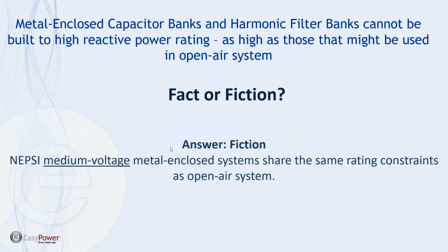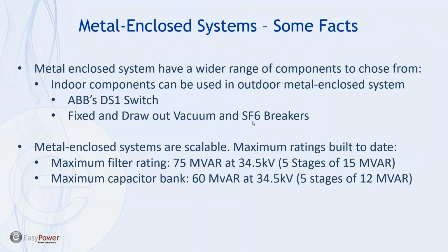So on to the next myth. Metal-enclosed capacitor banks and harmonic filter banks cannot be built to reactive power ratings as high as those that might be used in open air systems. Fact or fiction? We say fiction. Again, NEPSI's medium voltage metal-enclosed systems share the same rating constraints as open air systems. So the first thing to realize is metal-enclosed systems utilize all the same components as open air systems.